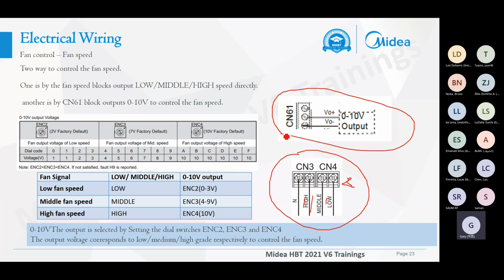If you use this point to control the fan speeds, there are rules to follow. The ENC2, the ENC3 and the ENC4 should have these relations. The ENC4 should be bigger than the ENC3, and ENC3 should be bigger than the ENC2. And normally for the 0 to 10 volt control, 2 volt is for the low speed, 7 volt is the middle speed, and 10 volt is for the high speed control.